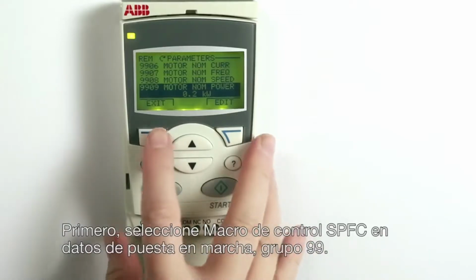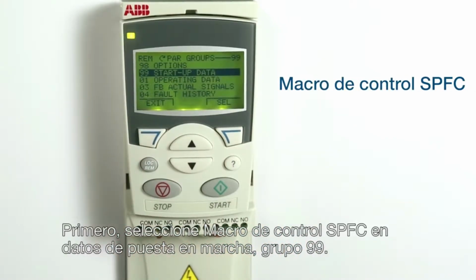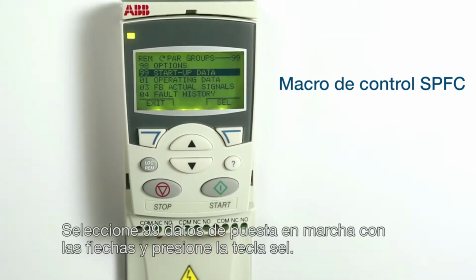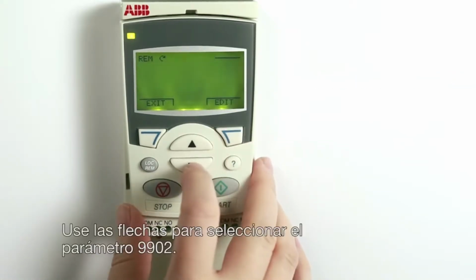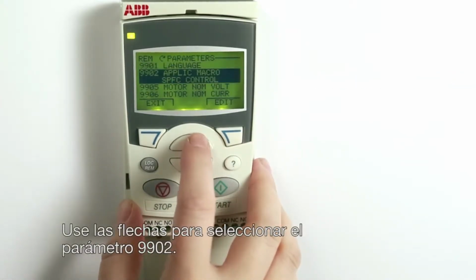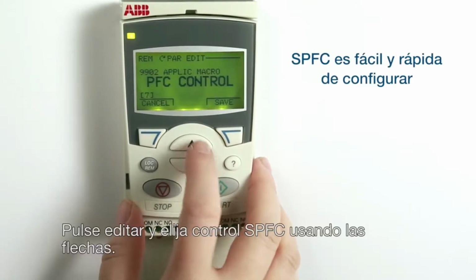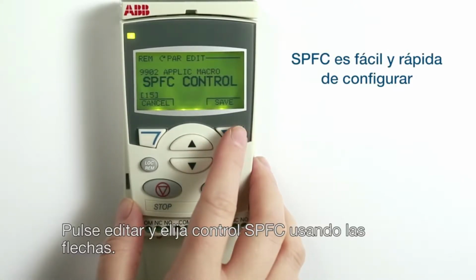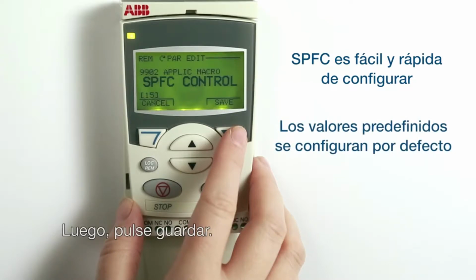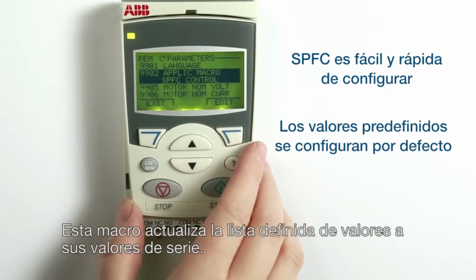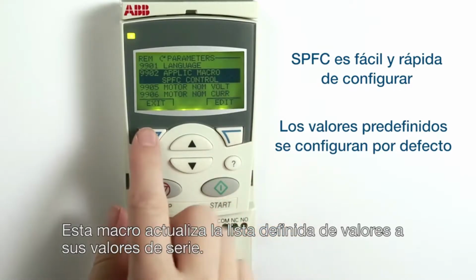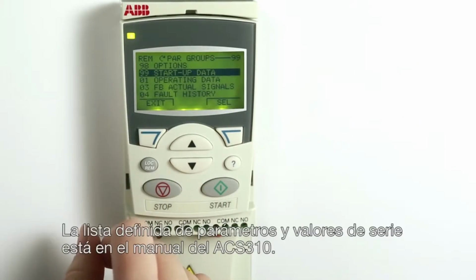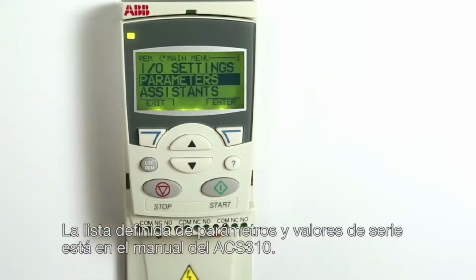We start by selecting SPFC Control Macro from Startup Data, parameter group 99. Choose 99 Startup Data with arrow keys and press Select. Use arrow keys to select parameter 9902. Press Edit and choose SPFC Control using arrow keys. Then press Save. This software macro updates the defined list of parameter values to their default values. The defined list of parameters and default values can be found in the ACS310 User's Manual.